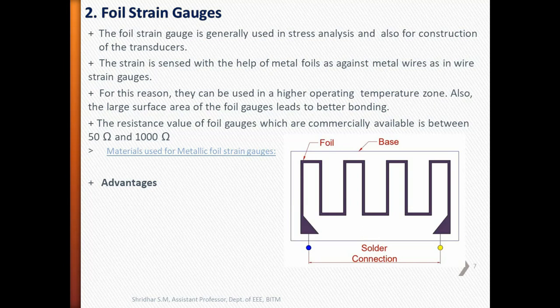Foil strain gauges. These gauges are used generally in stress analysis and also in the construction of transducers. The strain is sensed with the help of metal foil, as against metal wire in a wire strain gauge. The foil gauge has much greater dissipation capacity compared with wire wound gauges because of their greater surface area for the same volume. Due to this reason, they can be employed for higher operating temperature ranges.